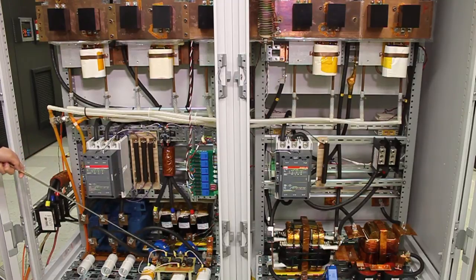There is a passive damping circuit for the filters, which has a very low loss. The common mode chokes are placed at both inverter side and the grid side. There are also pre-charge circuits, sensor board, and also fuses as the auxiliary circuit for the DC-AC part.